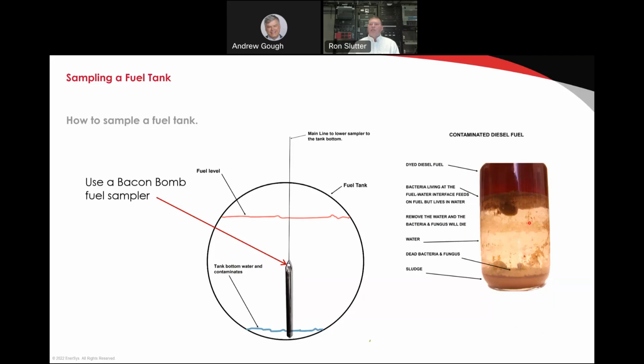If this were allowed to continue, and it will continue until you get it removed, and it does happen on almost every tank. Each tank will deal with it a little differently, but because they changed the requirements of diesel fuel in the industry, they've eliminated a lot of additives that allowed this process to slow. You need to deal with this. The first step in dealing with it is understanding what's going on.